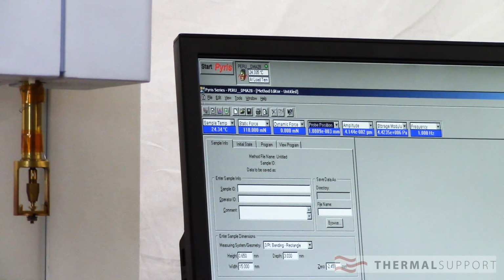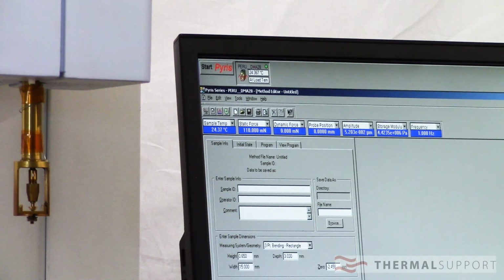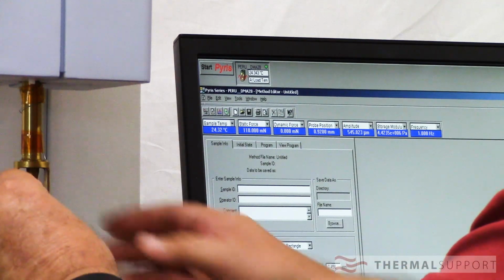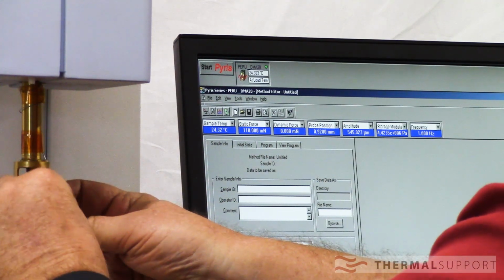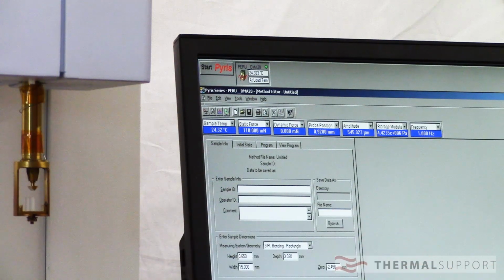You're going to set zero up when you do your runs. You're going to look at your height, read your height. So we're right down where we ought to be. What we care about now is the span, the 10 millimeters. So I'm going to automatically re-zero this. Then I'm going to scoot in here a second and put our 10 millimeter quartz standard up there again. I'd use my tweezers, except I really stink with the tweezers. Maybe not so much when I was younger.